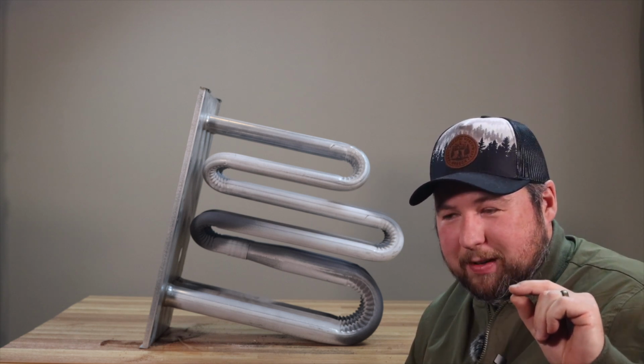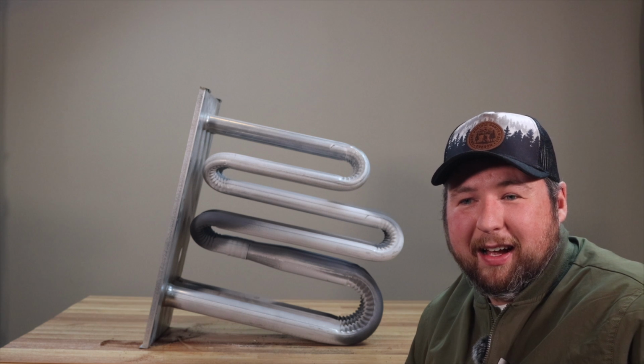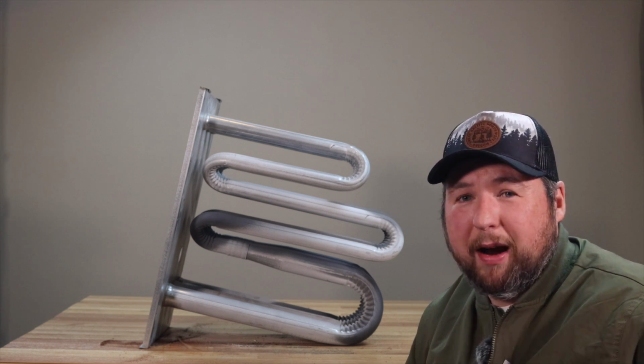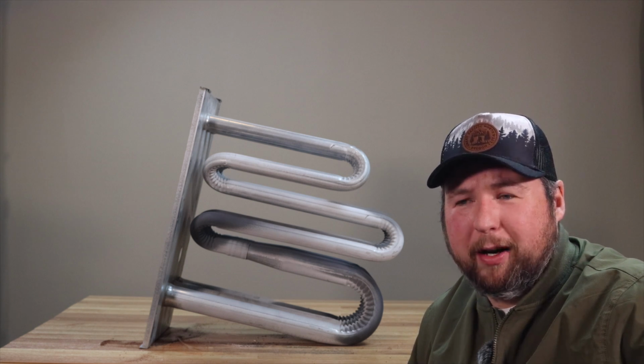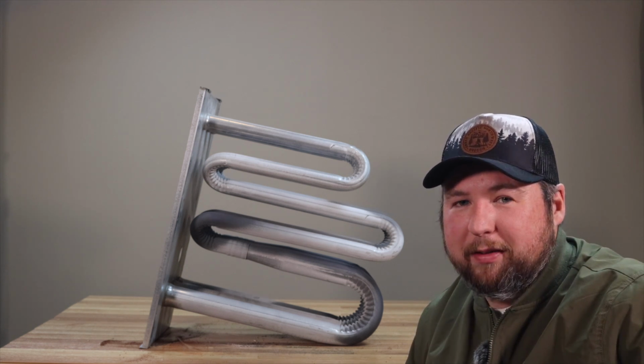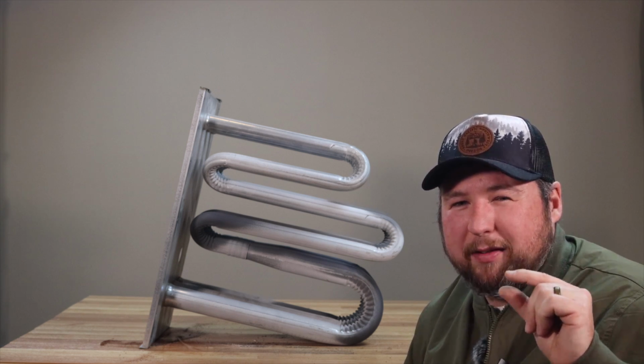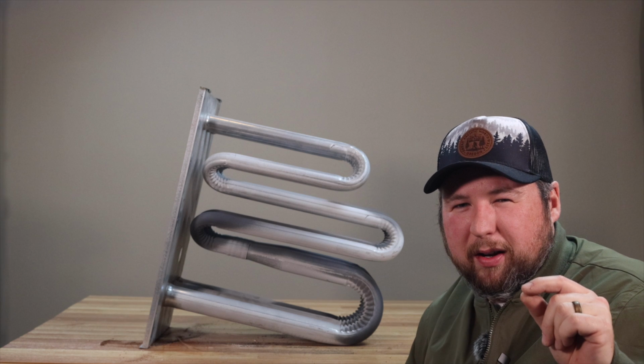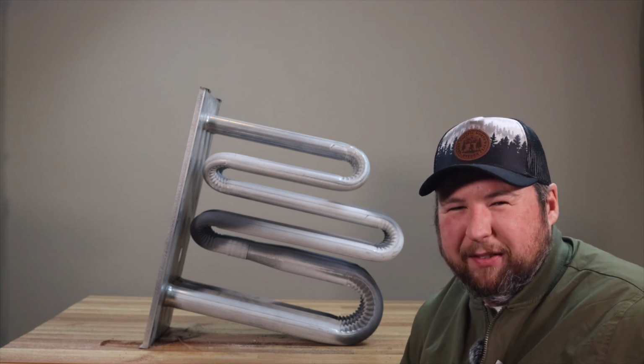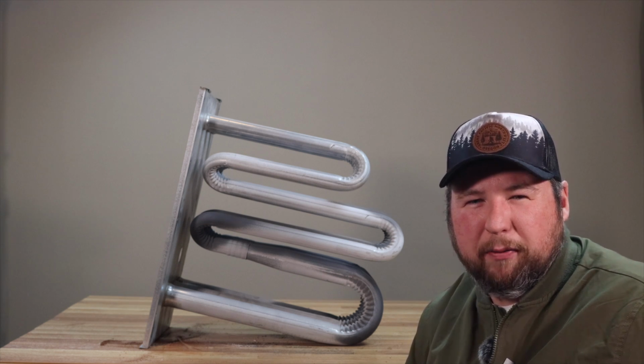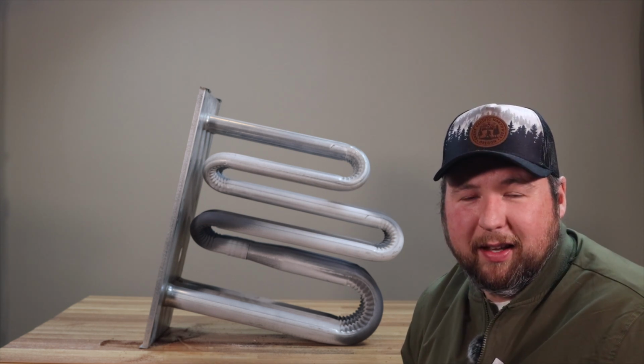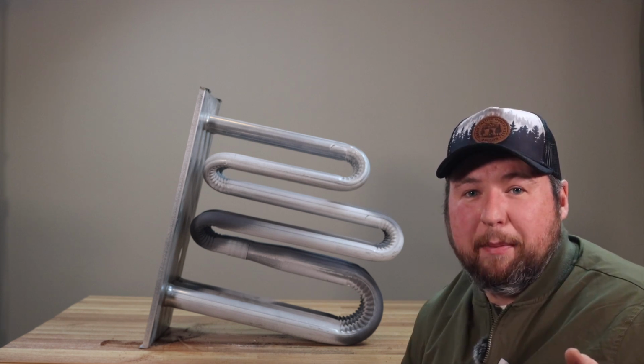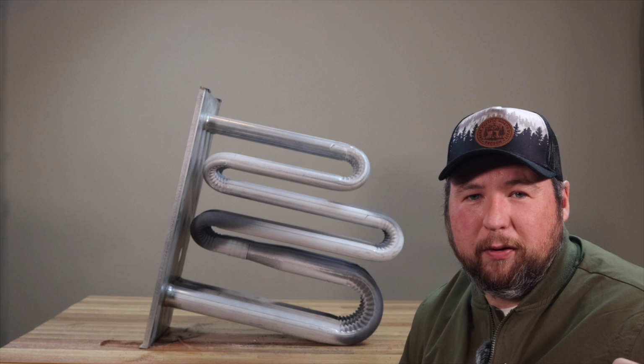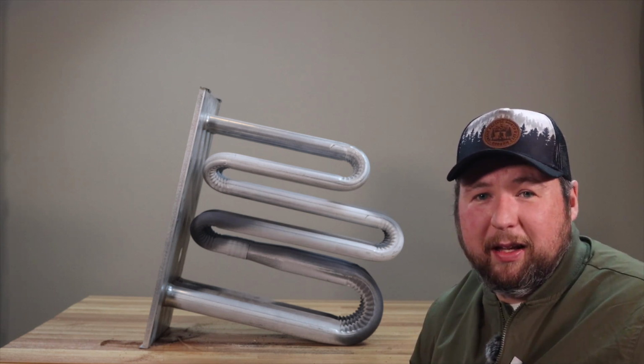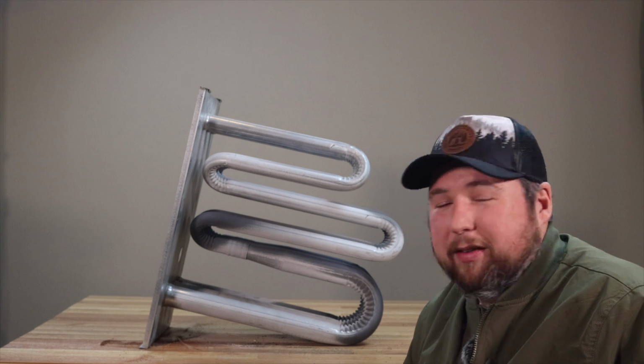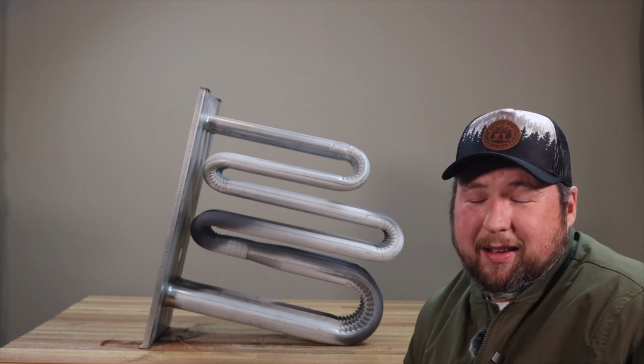Also, there is some fine print when it comes to that. I'm not sure if this has changed. I've tried to find the document online because I used to have it printed out, but I don't have it anymore. Basically, there's some fine print when it comes to cracks, like it has to be a certain size to constitute having to replace it. If it's an itty bitty tiny little crack, I think they say you want to monitor it, but it's recommended to replace the heat exchanger, because a tiny little crack is going to get bigger. Once it's compromised, it just gets worse over time. So if you find a tiny one, it's going to turn into a big one eventually. Honestly, if I find even a tiny little hairline crack, I say, hey, you need to change the heat exchanger.